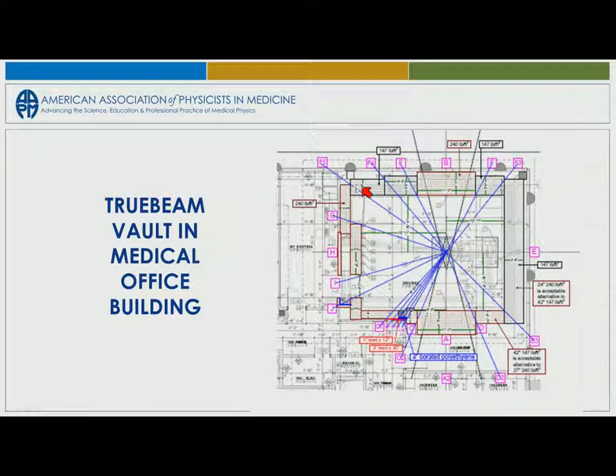So this is where we went with this: this is all 147, but this is 240. This is your primary barrier, and that's driven because this is the limit of the building. They didn't have room to go out there and go extra feet. So that's what you wind up doing. Now, what else is different about this room compared to the traditional maze LINAC? There is no maze.